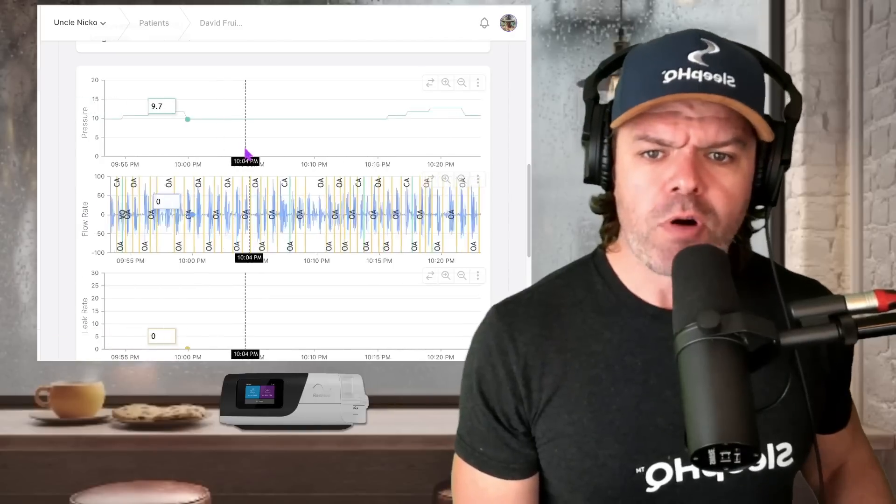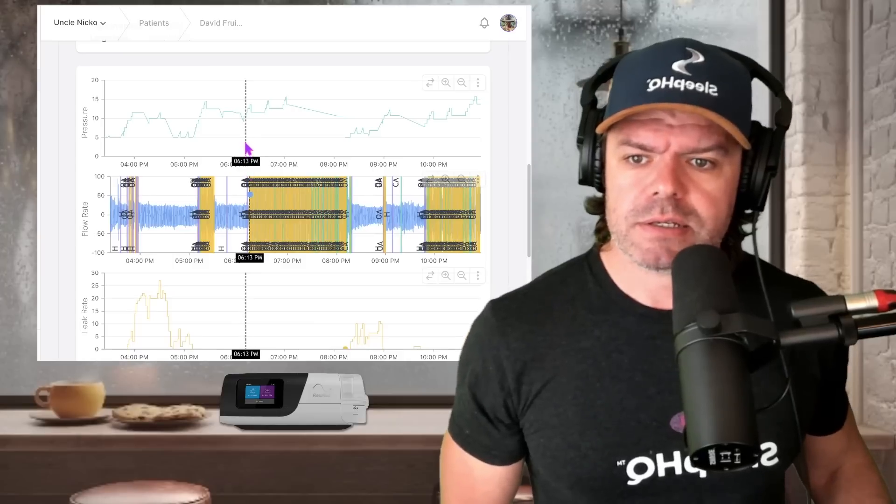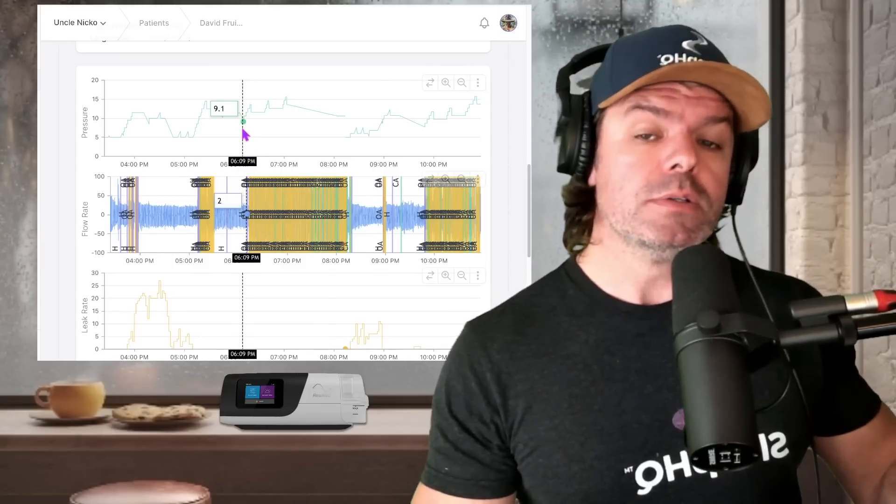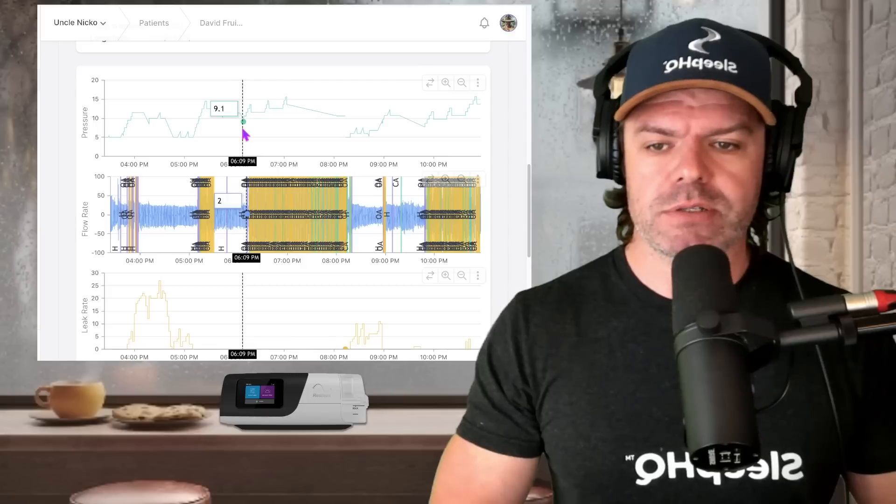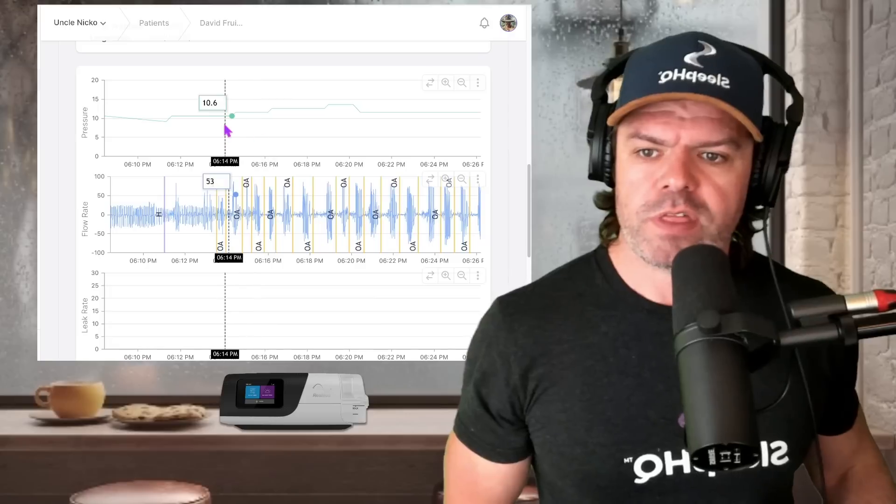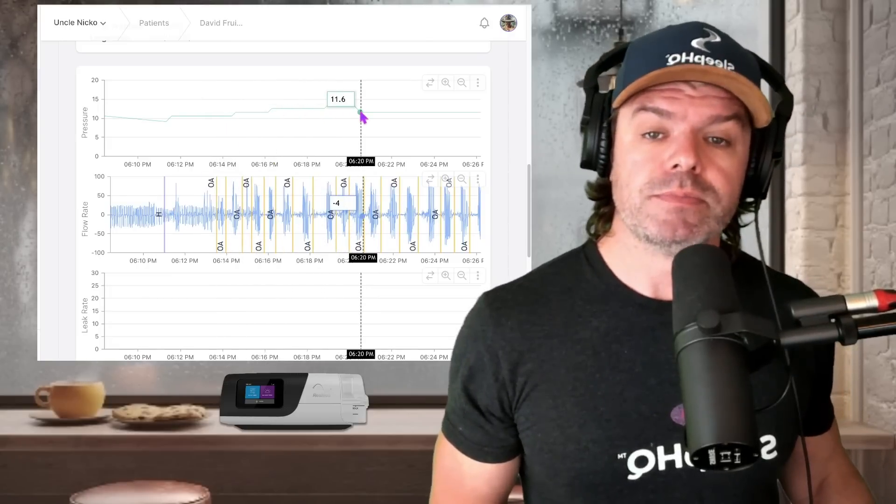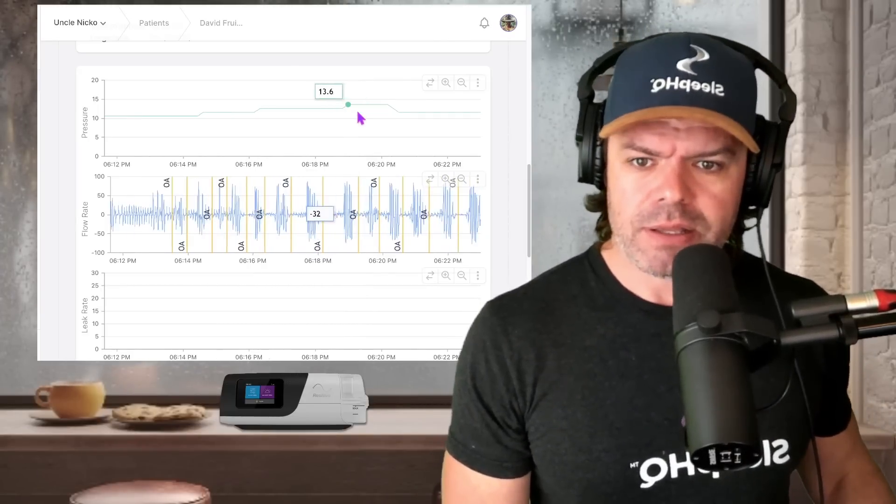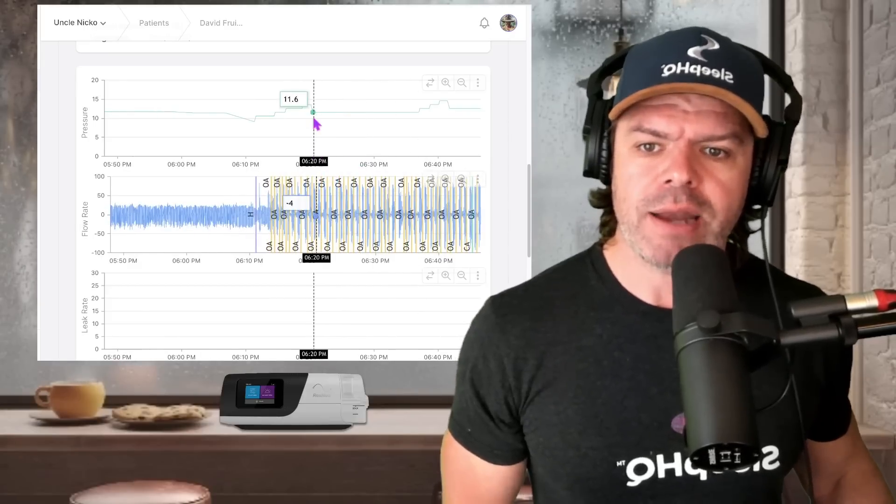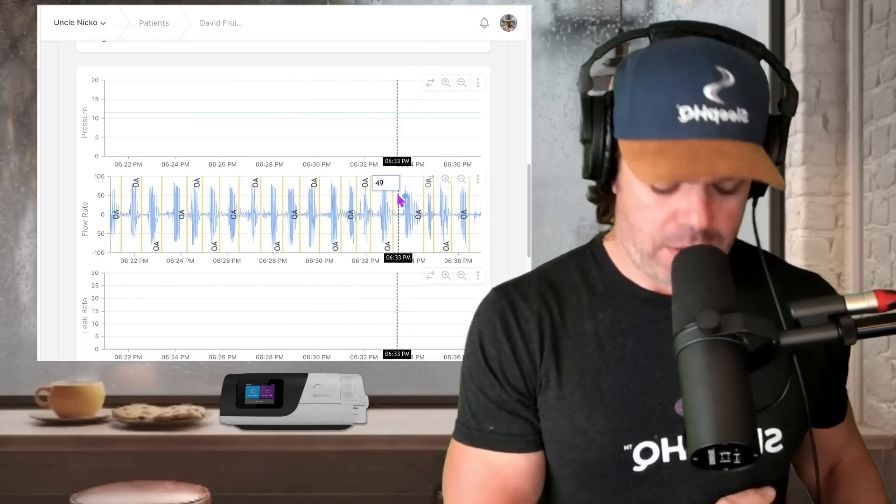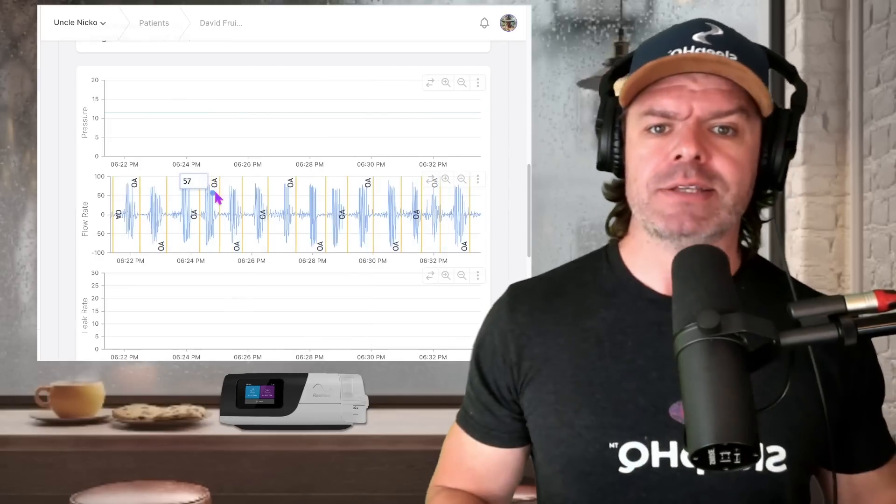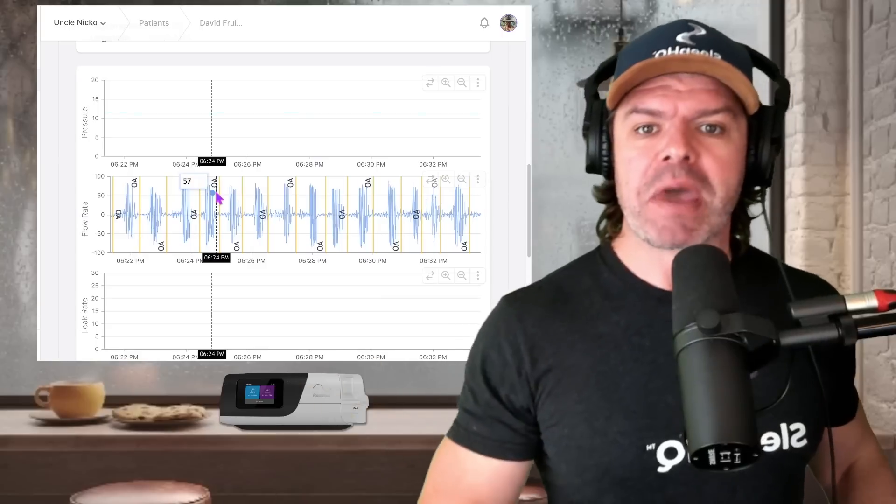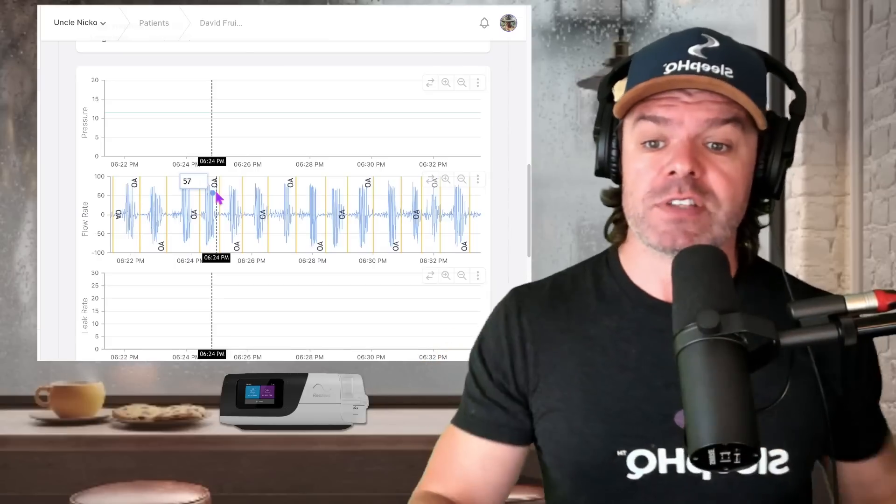So the big problem, the big problem I have with the Philips algorithm right here is it's taking way too long to increase the pressure and treat those sleep apnea events. And I'll show you how ResMed does it in a second, which is 10 times better. I don't have an issue personally with them doing this little step up, step up, step up, and then step down to make sure that they're not inducing central apnea. However, you can't, you know, in this little section here, there is no central apnea flag. So you can't keep the pressure at the same low rate with all this obstructive apnea happening for 15 minutes. Not on. That's rubbish. This isn't some sort of really complex case with lots of central apnea, mixed apnea, high leak rates, mouth leak rates, where the automatic algorithm can't figure out what's going on.